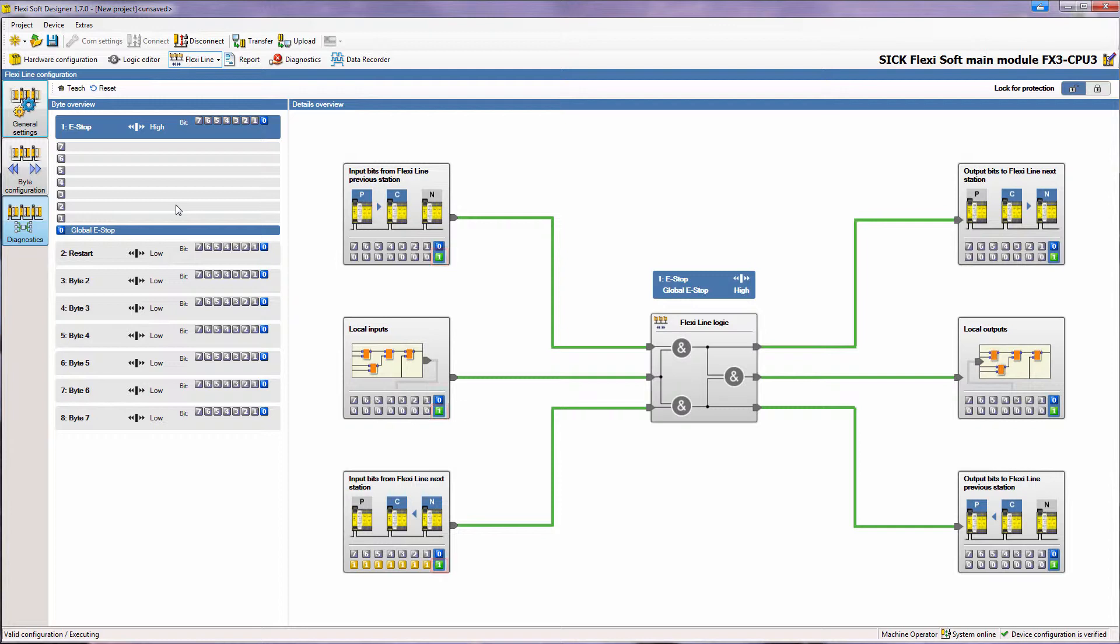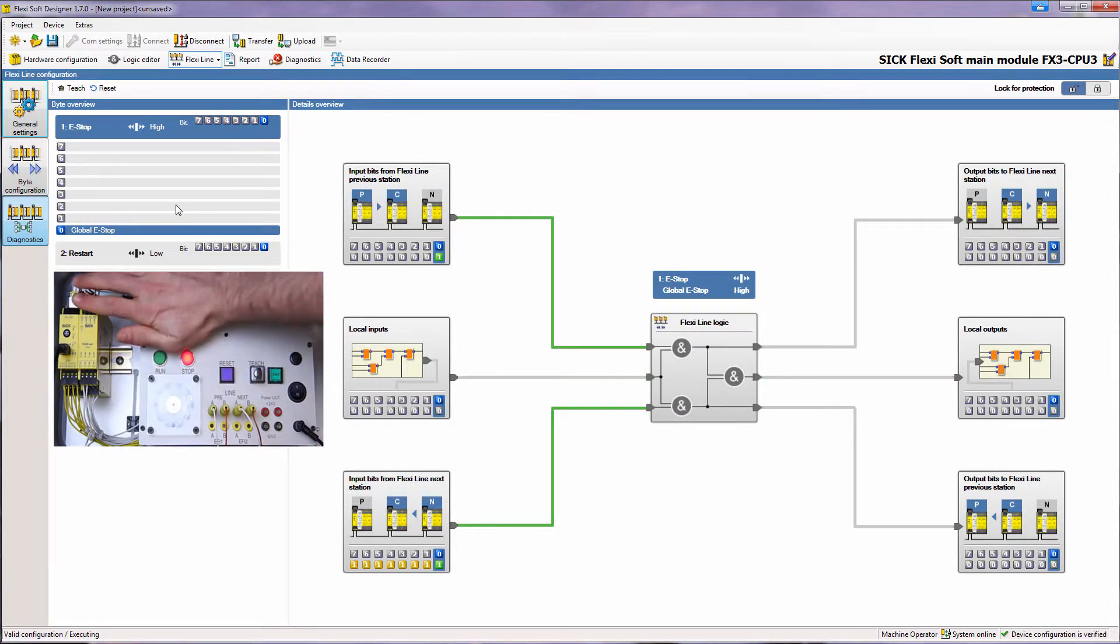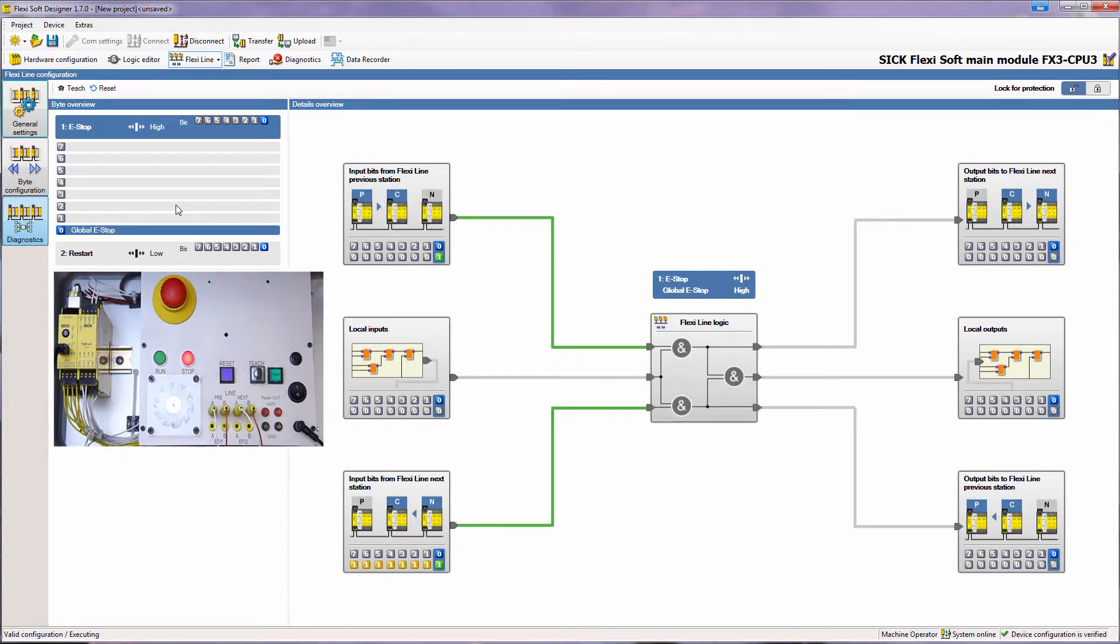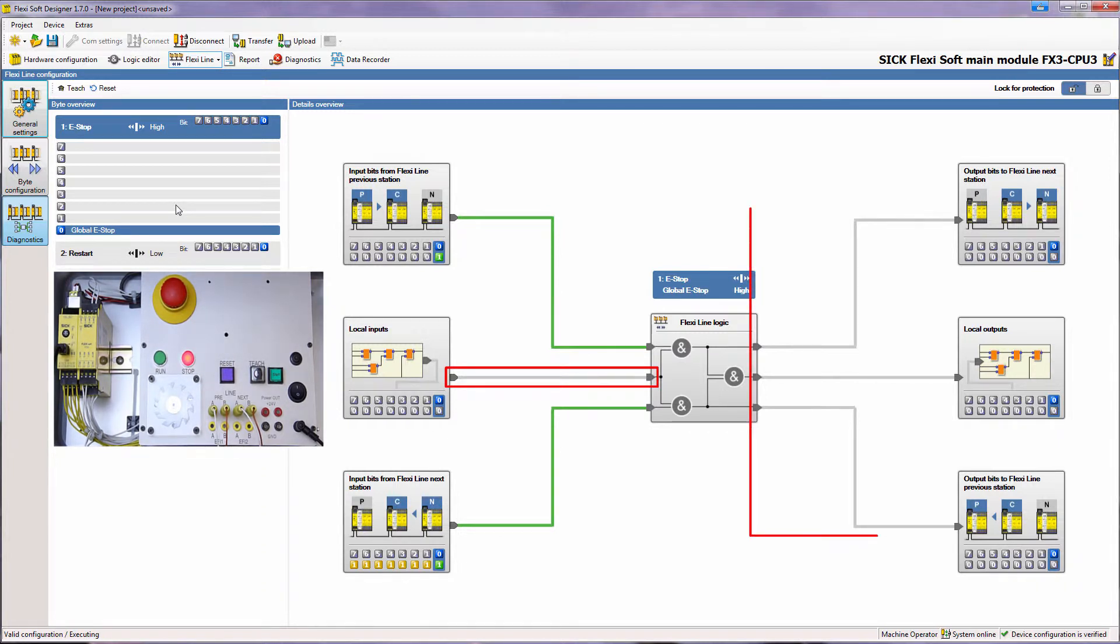Now I press the e-stop on station 2 which is connected to the FSD. The actuators of all demo cases stop. The global e-stop bit of the local inputs as well as the connection to the FlexiLine logic has changed to grey. This low signal was processed via the FlexiLine logic to the output bits, and the result has been the stop of all the stations within the FlexiLine system.